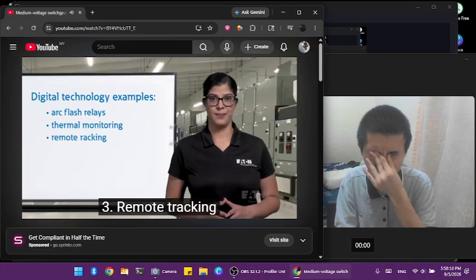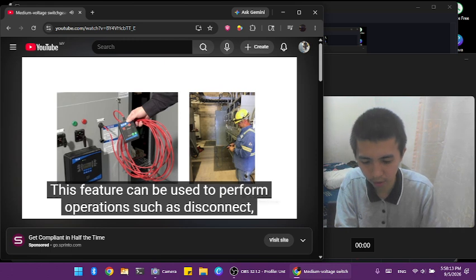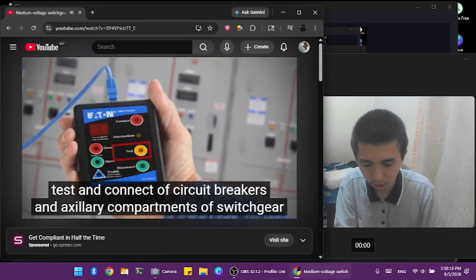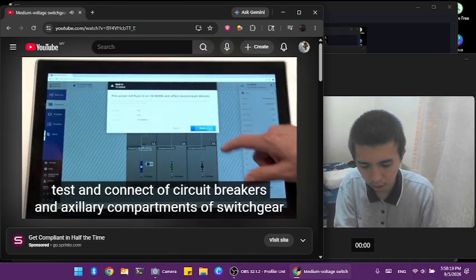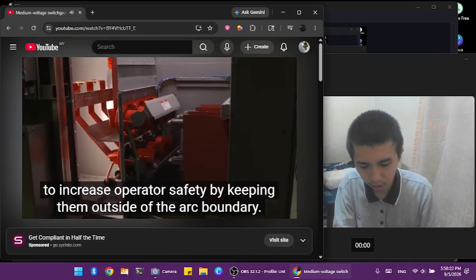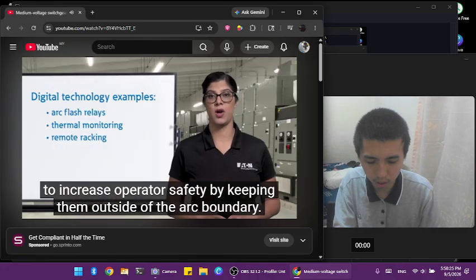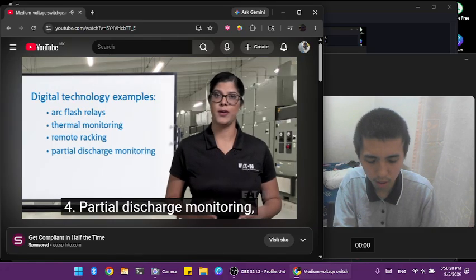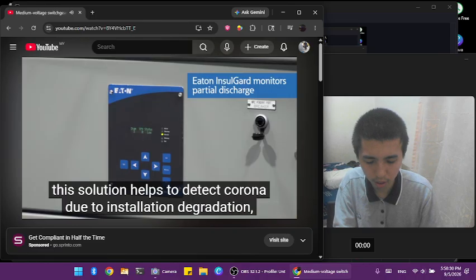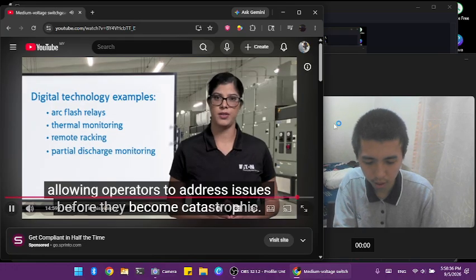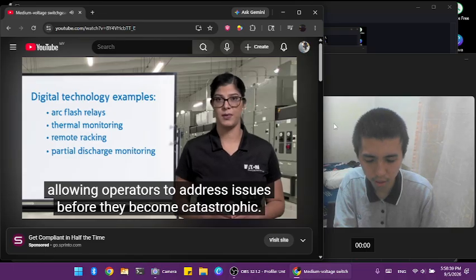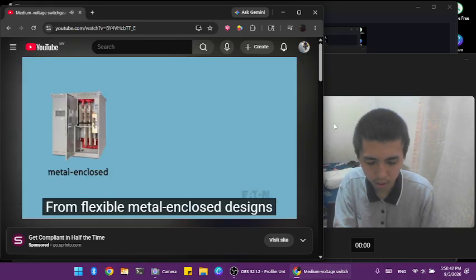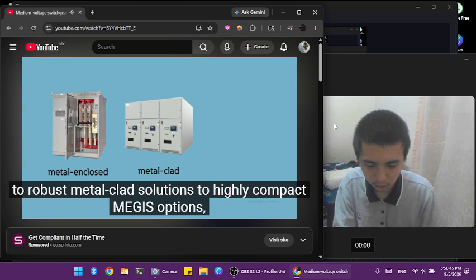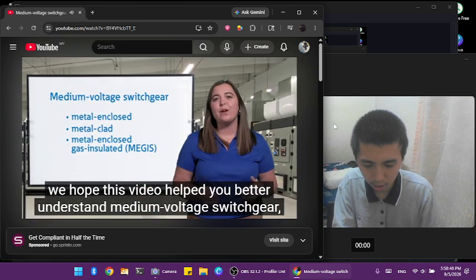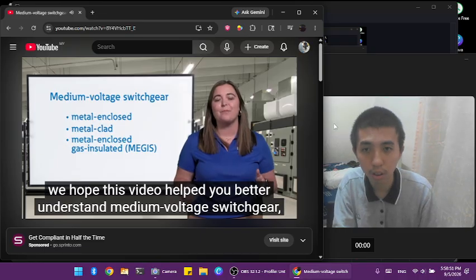3. Remote racking. This feature can be used to perform operations such as disconnect, test, and connect of circuit breakers and auxiliary compartments of switchgear to increase operator safety by keeping them outside of the arc flash boundary. 4. Partial discharge monitoring. This solution helps detect corona due to insulation degradation, allowing operators to address issues before they become catastrophic. From flexible metal enclosed designs to robust metal clad solutions to highly compact MEGIS options, we hope this video helped you better understand medium voltage switchgear.